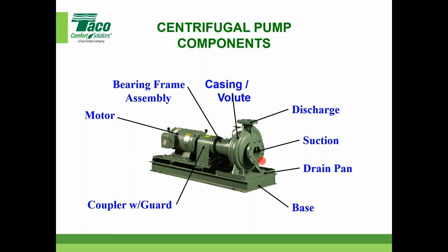Drain pan. It does extend far enough out in ours to catch any dripping that takes place here. There's the suction. You can see the flange here. There's a little vane there, and many of us in the industry have that, and that's just another way to help straighten the water as it comes into the volute, the wet end, the casing. Very, very important. It does not replace a suction diffuser or straight run of pipe. It does not replace good engineering practice, but it's just another way to help straighten stuff as it goes in.